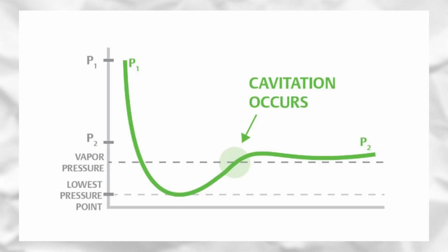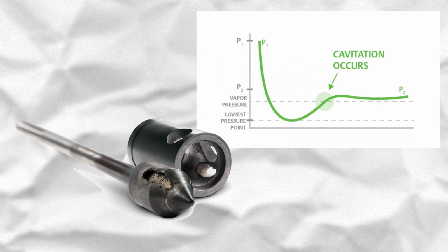A plug would close the path of flow which moves through the valve port. The further the plug is from the seat, the more flow can pass through a valve. As I explained before, a control valve creates a delta P. As a result, flow could be controlled. One of the most important factors to design a valve is that the downstream pressure, the outlet valve pressure, must not be less than fluid vapor pressure. Otherwise, fluid is vaporized inside of the valve and forms bubbles which move with high velocity and cause a lot of damage to valve trim. This severe service is known as the cavitation phenomenon.